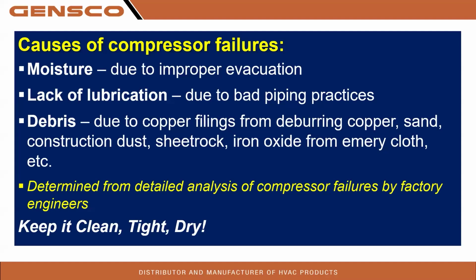Debris: copper filings from deburring copper, sand, dirt, construction dust, sheetrock dust, iron oxide from emery cloth, etc., something from the installation process. And these major reasons have been determined from detailed analysis of compressors the factory asked for back, which their engineers actually tore down to analyze what caused the failure.